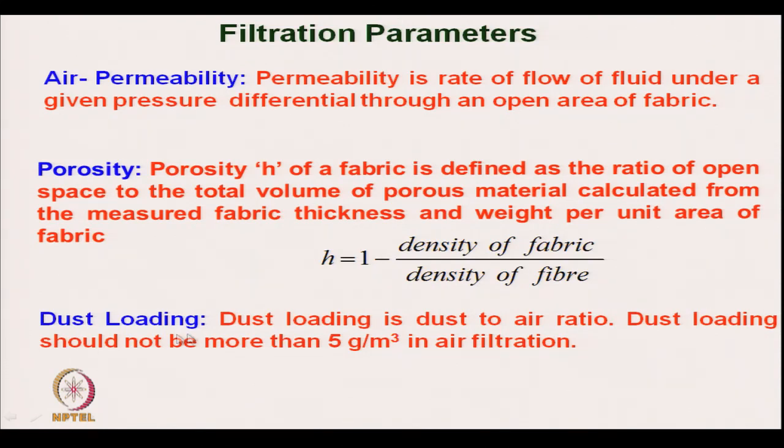Dust loading is the dust to air ratio. Dust loading should be less than 5 gram per meter cube. Okay.